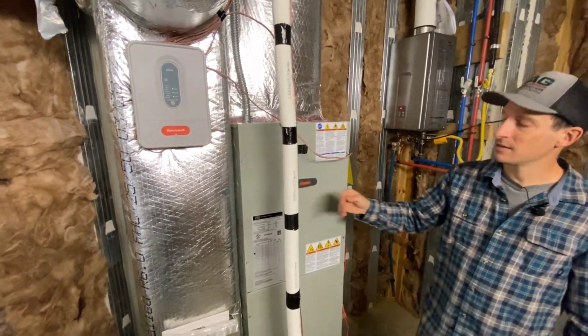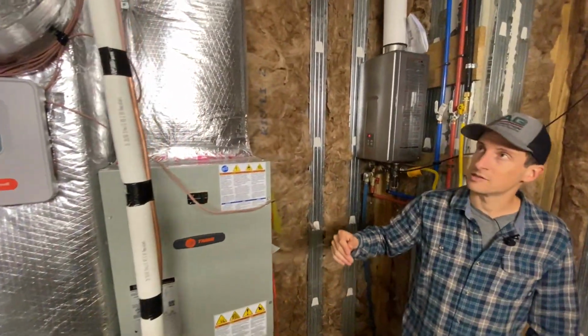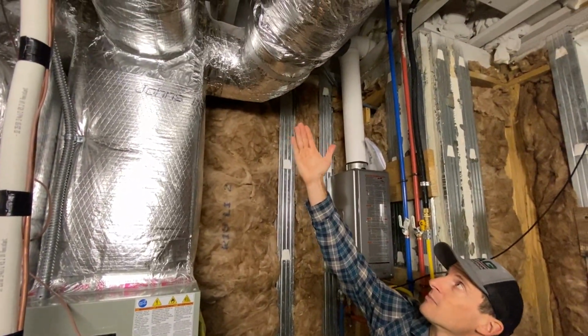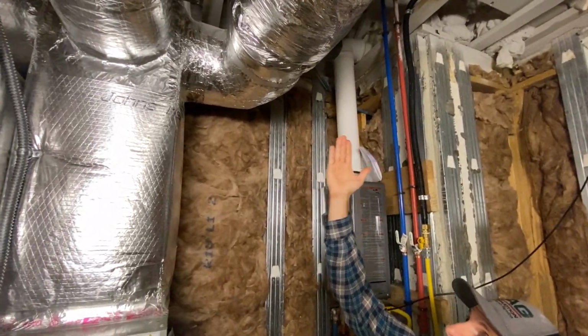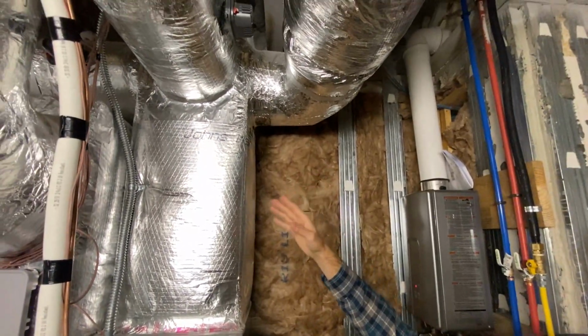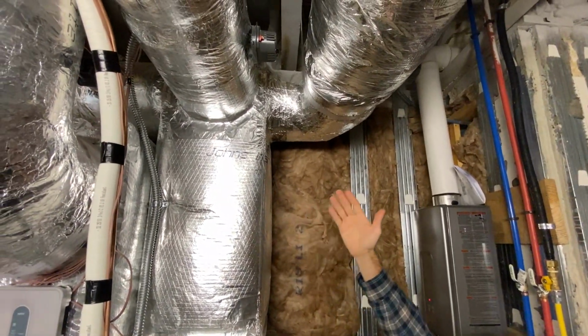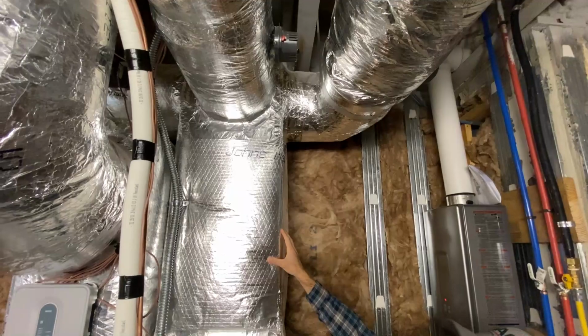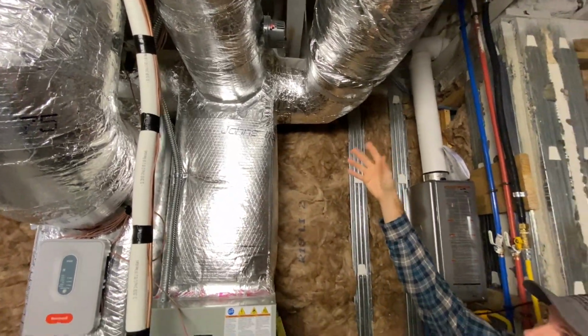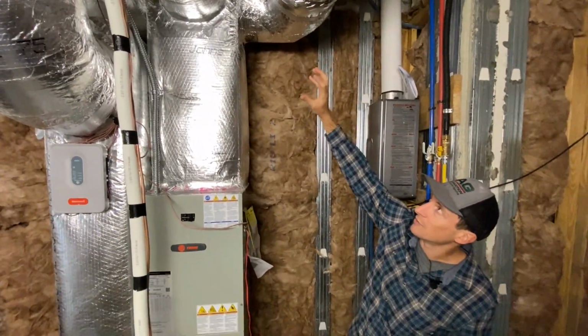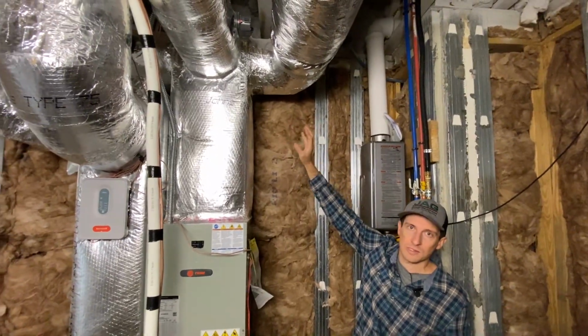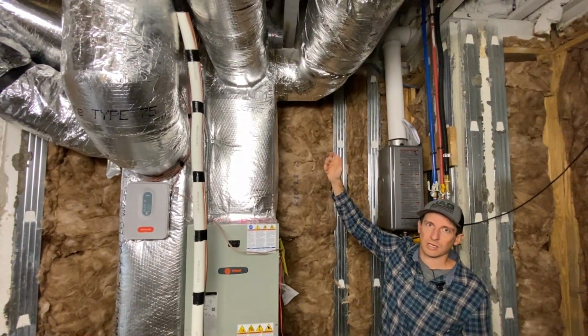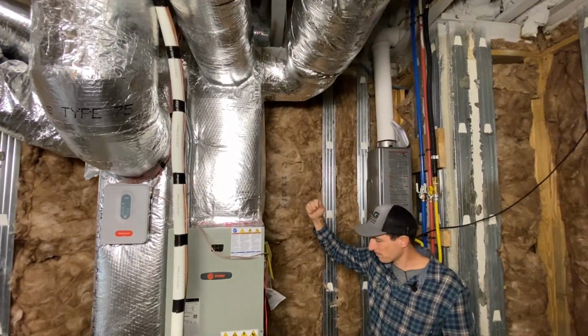This brain is then connected to what are called zone control dampers, and you can see them on the side of the ductwork here. So this unit has 3 zones, so it's got 3 pipes kind of exiting the main pipe here, and each one of those zones has a damper inside of it that either opens or closes depending on if you're calling for heating or cooling in that portion of the home.